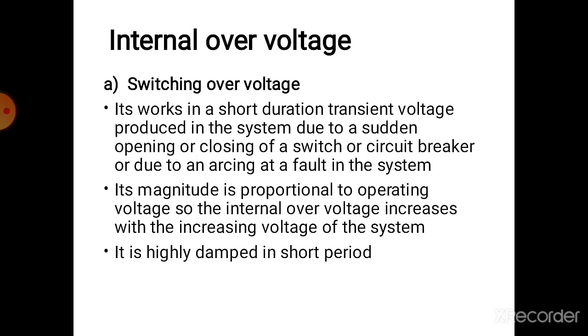Internal overvoltage is also known as switching overvoltage. Switching overvoltage is a short duration transient voltage produced in a system due to the sudden opening and closing of a circuit breaker, or due to arcing at a fault in the system. Its magnitude is proportional to the operating voltage, so internal overvoltage increases with the increasing voltage of the system.